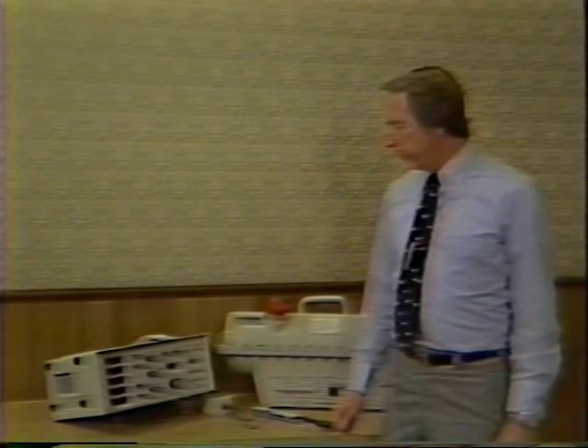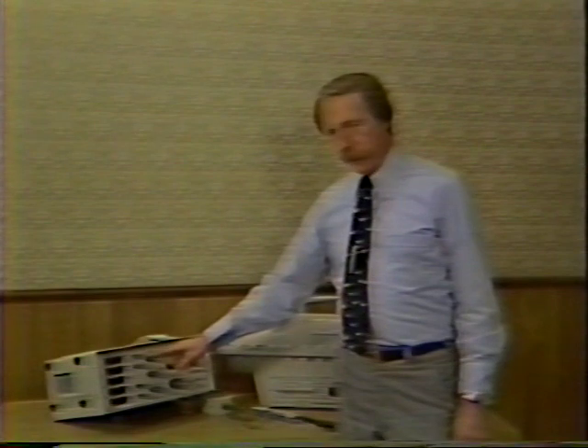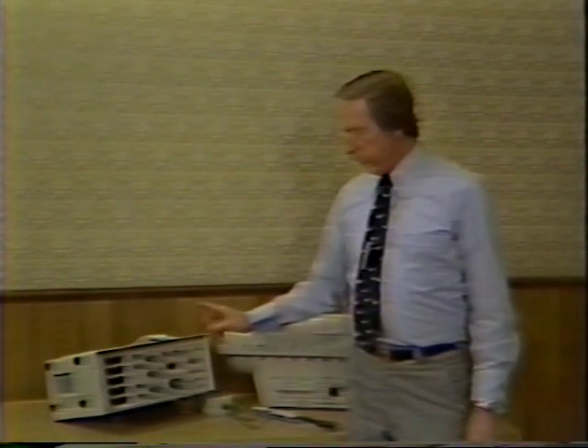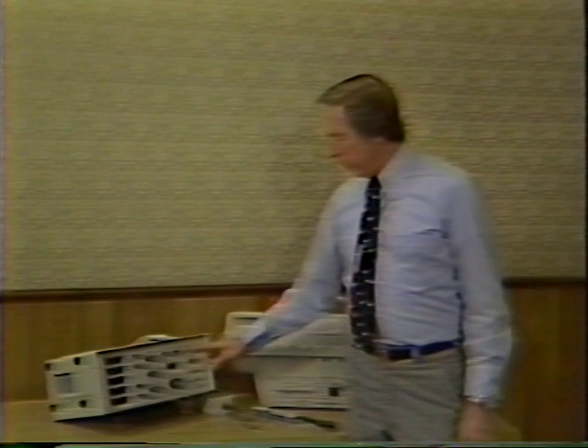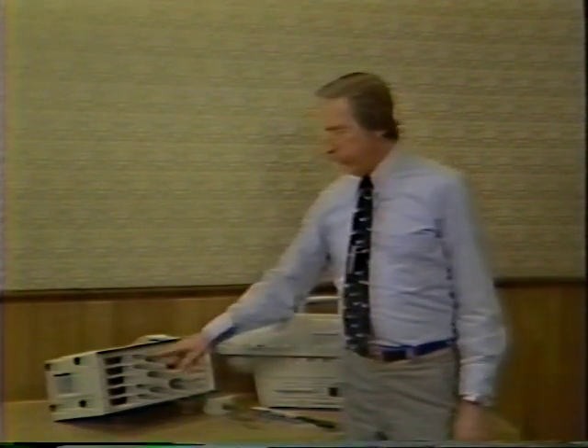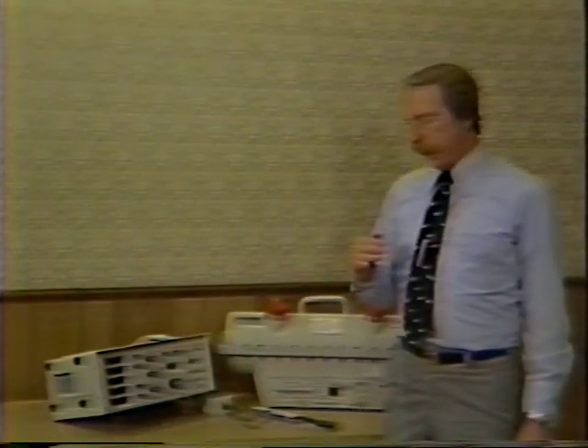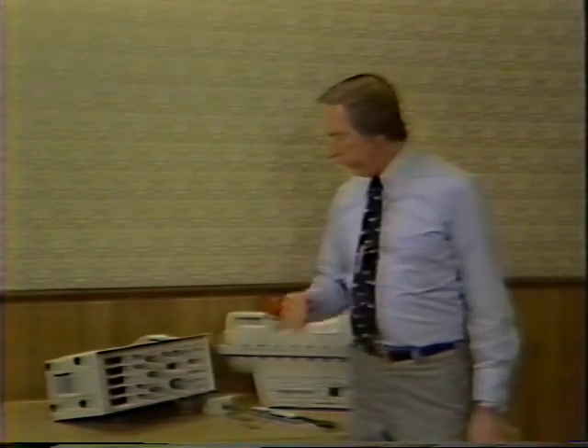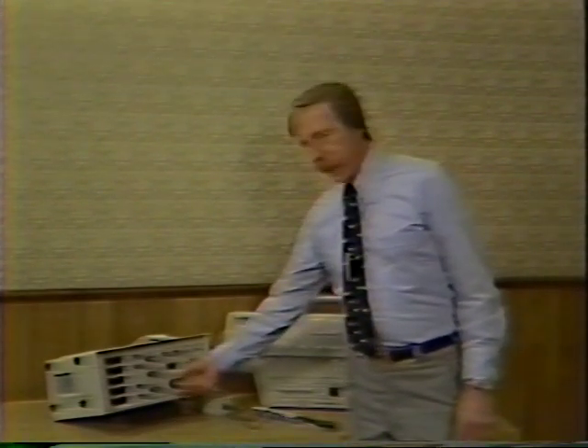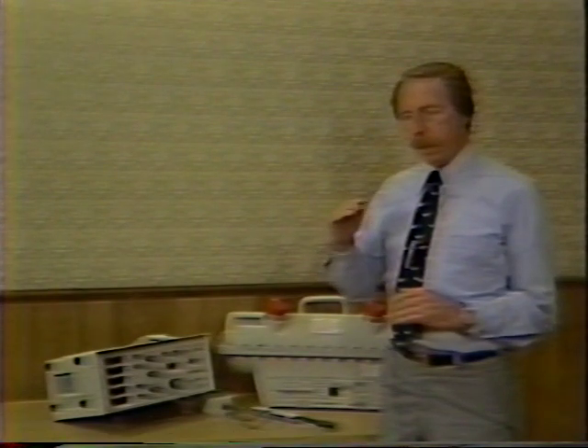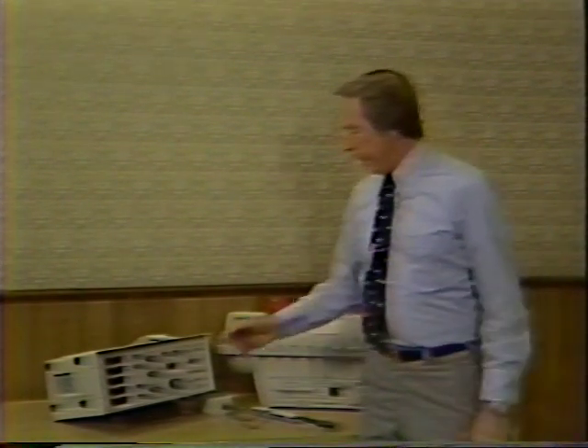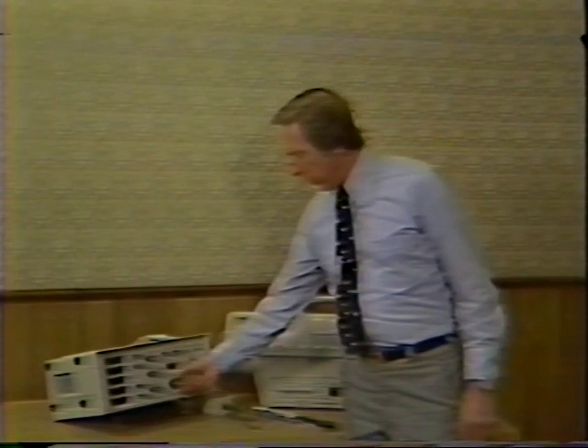In the other position of the switch, preset, or commonly called manual, we are going to dial in the absolute value of the signal that we're triggering from. Thus, we do not calculate automatically. We have to do it manually. Let's use those same values again. 100 kV set into the generator. It's a GE equipment, three-phase. We would then dial in 75 kV. If we move the input generator voltage up to 120 kV, we would then have to calculate ourselves and dial in 75% of that value, or 90 kV here.